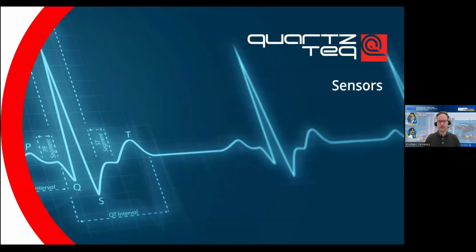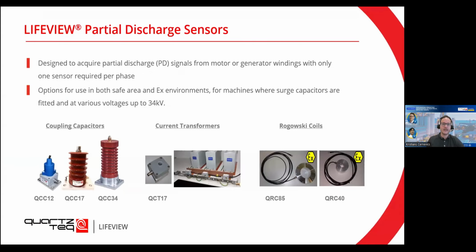I talked about all these measurements and how we analyze the data, and of course you need sensors to capture this data. So let me show you the types of sensors we actually have for partial discharges. There are essentially three main types. The first one is the coupling capacitor, the second type is the current transformer, and finally you have the Rogowski coils. They're designed to work on one particular phase, so you only need one sensor per phase on a motor or generator. And there are options for essentially three different cases.